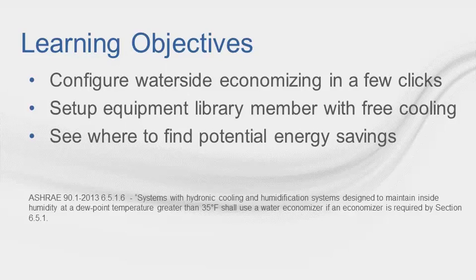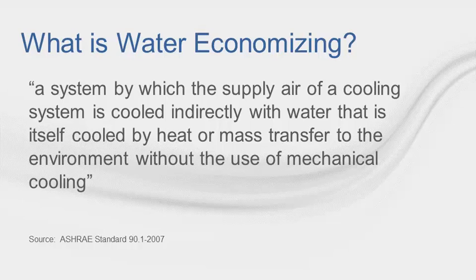It's worth noting that ASHRAE Standard 90.1-2013 requires waterside economizers for systems with hydronic cooling and humidification systems designed to maintain a dew point greater than 35°F, when an economizer is already required per Section 6.5.1. ASHRAE defines a water economizer as a system by which the supply air of a cooling system is cooled indirectly with water that is itself cooled by heat or mass transfer to the environment without the use of mechanical cooling. In short, it's a system that lets you run your compressor less, or even not at all, during periods where conditions are favorable.